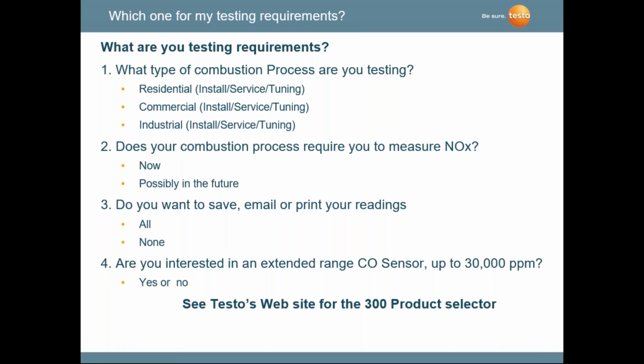So if you're looking at a combustion analyzer, there's 3 or 4 questions you need to ask yourself. Number 1 is, what is your combustion process? If you're doing strictly residential and oil burners, residential light applications, you may not need a 300. We do have a 310, which covers just the residential market. The 300 is designed more for if you're doing residential, commercial together, commercial, industrial. This is where you get into a 300. Does your combustion process require you to measure NOx? Not only does it require you to measure NOx now, but maybe next year you're going to be measuring NOx. If that's the case, then you need to get a 300 that has NOx capability, and I'll show you that in a second.